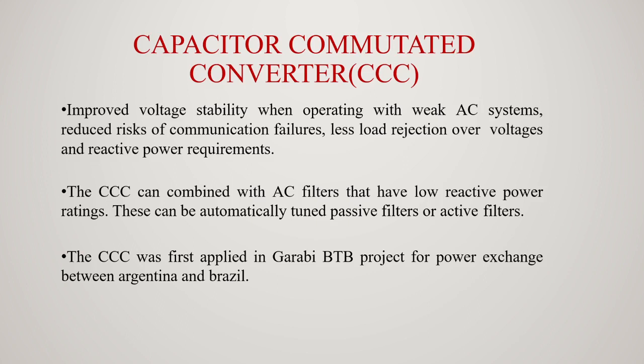Advantages of CCC are improved voltage stability when operating with weak AC systems, reduced risk of commutation failures, less load rejection overvoltages, and reactive power requirements. The CCC can be combined with AC filters that have low reactive power ratings, and these can be automatically tuned passive filters or active filters.